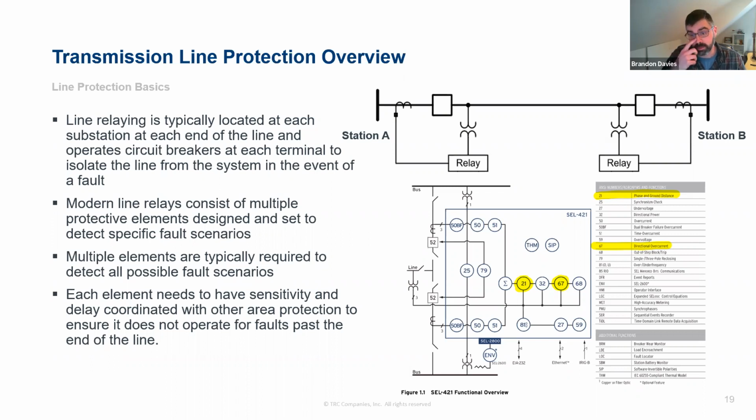And then the day three slide deck, which will probably start next Thursday and finish up the following Tuesday, is going into pilot protection, which is kind of an interesting, a little bit different approach to line protection, where the relays at each terminal communicate with each other to share information and make a better informed decision about whether or not the fault is on the line or not on the line, or if they need to make an operation. So that's kind of the plan for today, and then beyond, to wrap up the transmission line protection portion of the class.